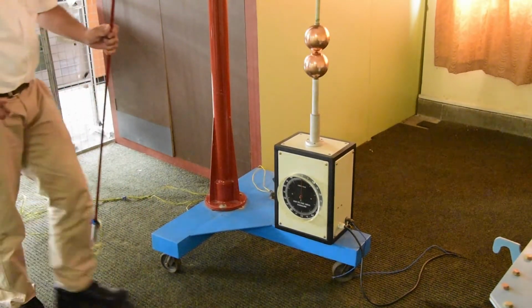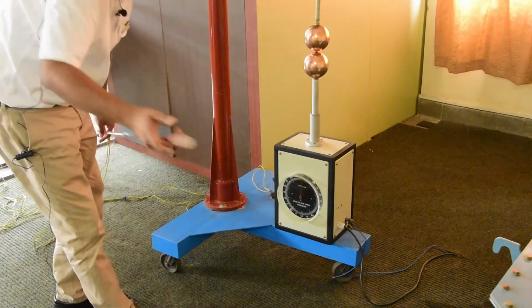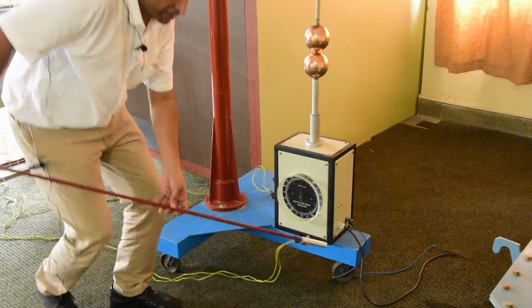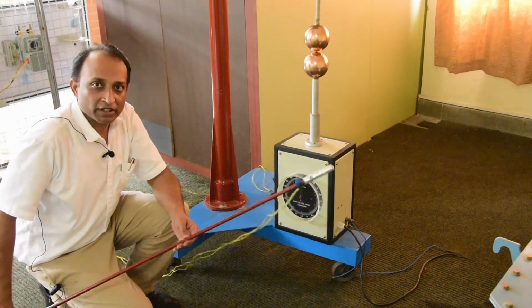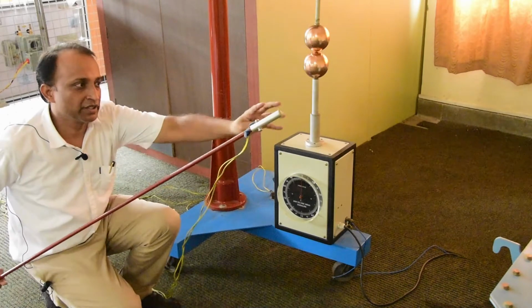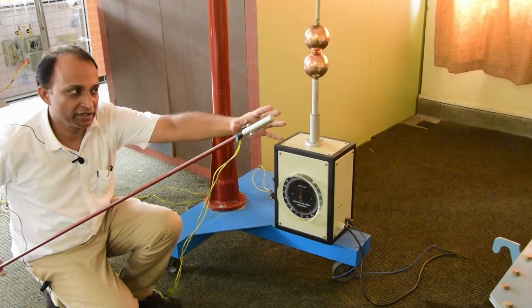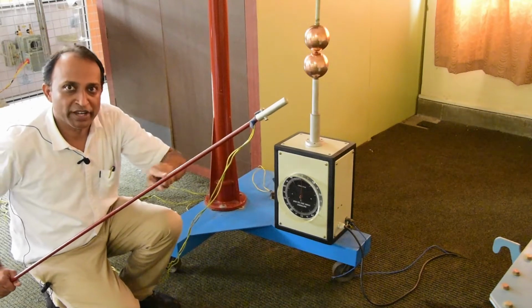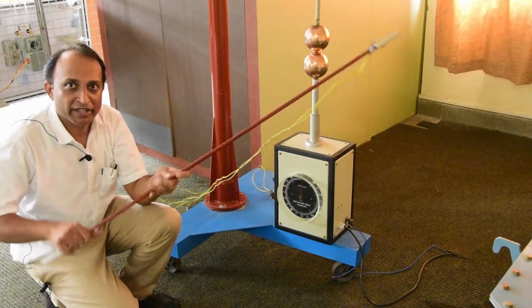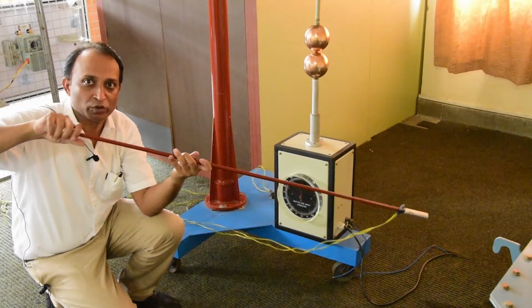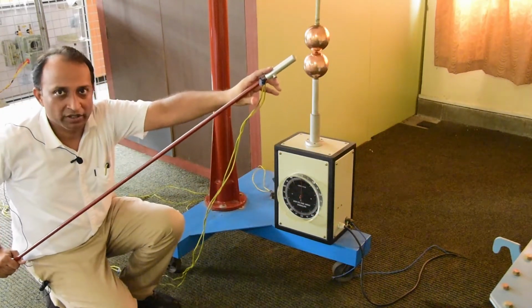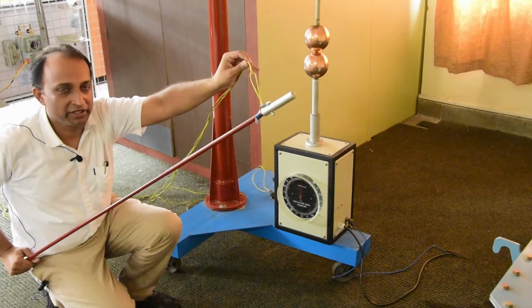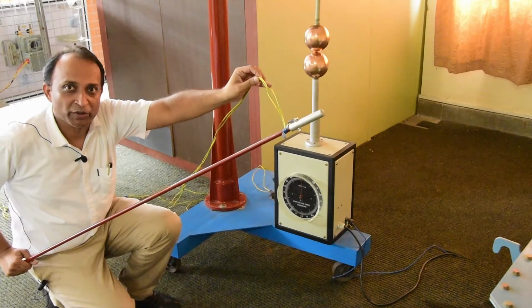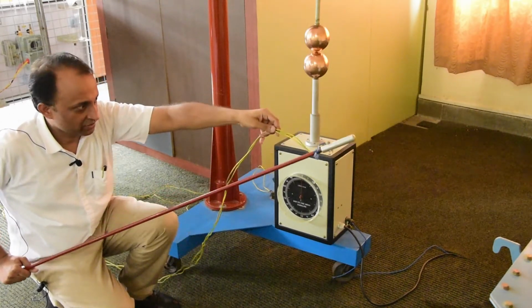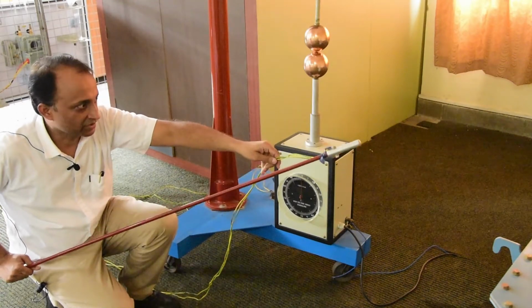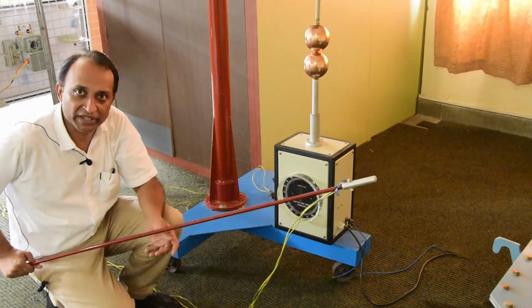I would like to show here that this is a grounding rod. Please pay attention that this is a grounding rod. It has a metal terminal brought out here, then this is the insulating rod, and then a fiberglass handle for personnel to hold it. This particular metal has a solidly grounded connection. These wires are grounded through the earth pit. There are 3 earth pits provided, 3 solid earthings for this whole assembly.